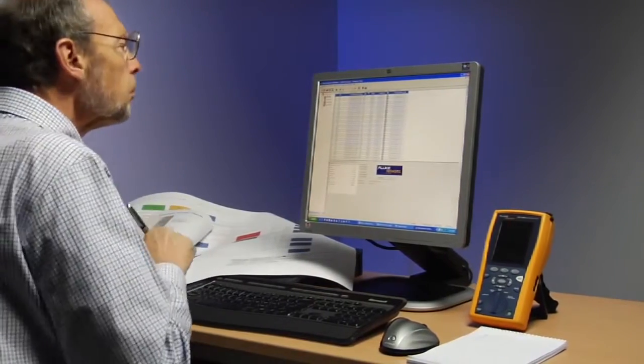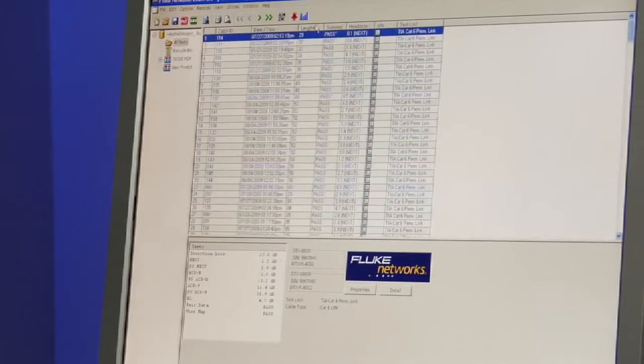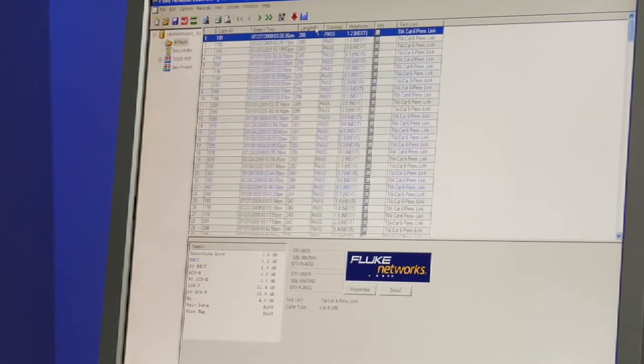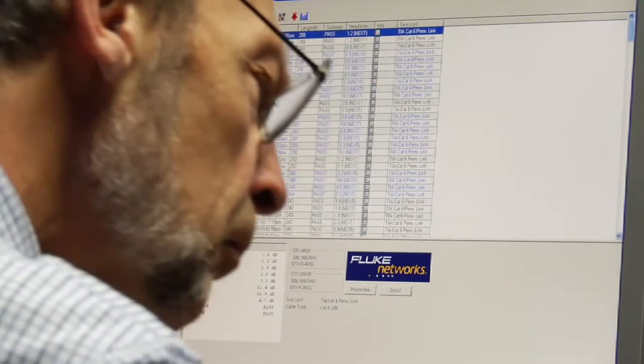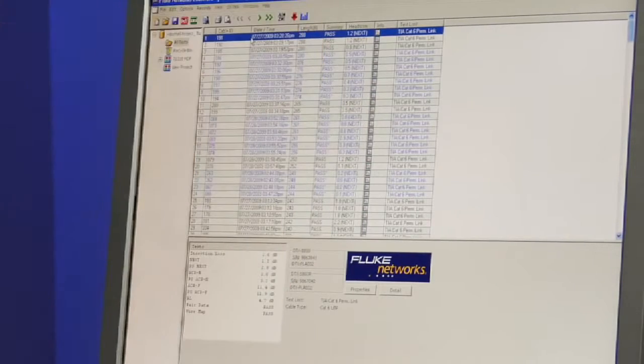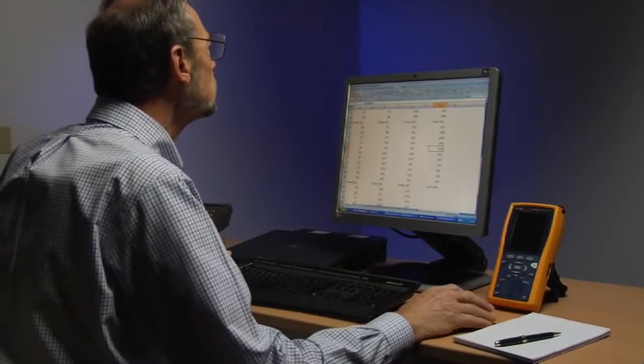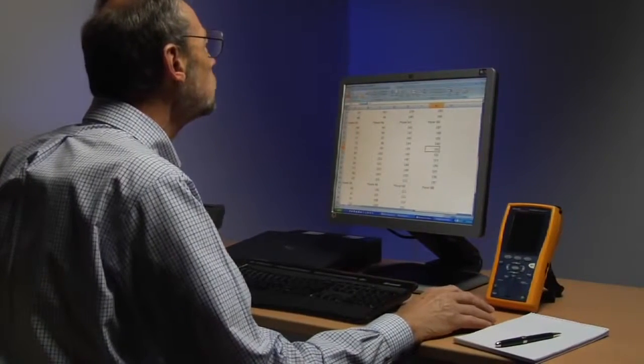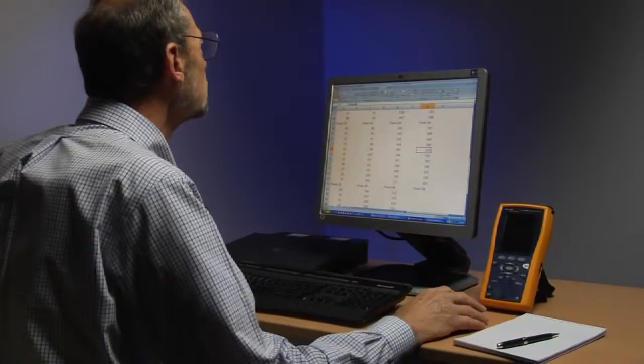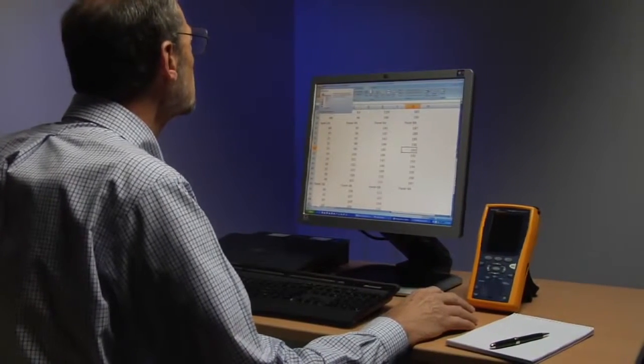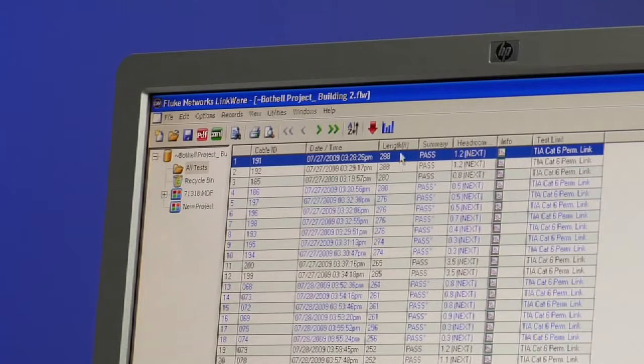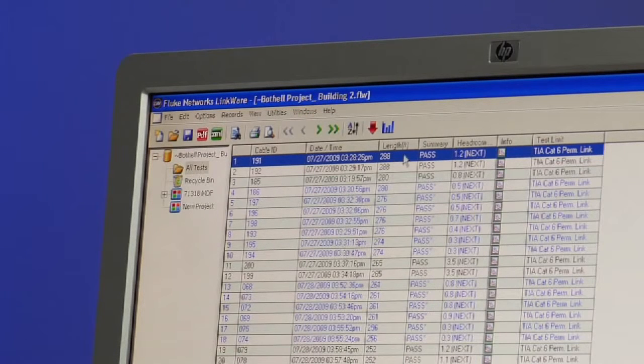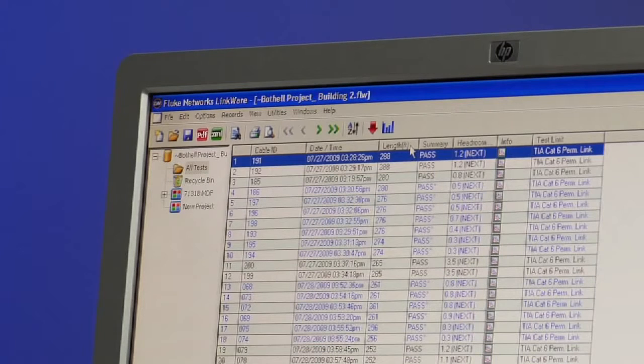We'll call these the victim links. Here you can see that we've already loaded the in-channel test results, and we're going to store the alien crosstalk files in the same job site folder. Project managers can do this in the office once in-channel certification has been performed, or technicians can do this planning on-site with a laptop.